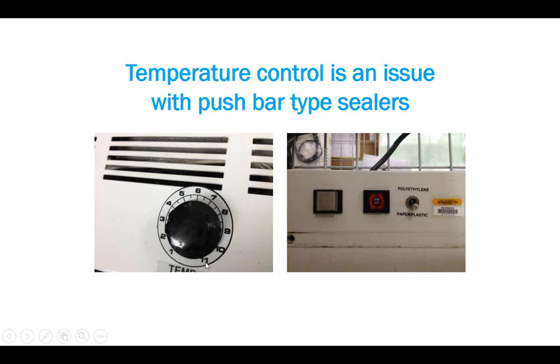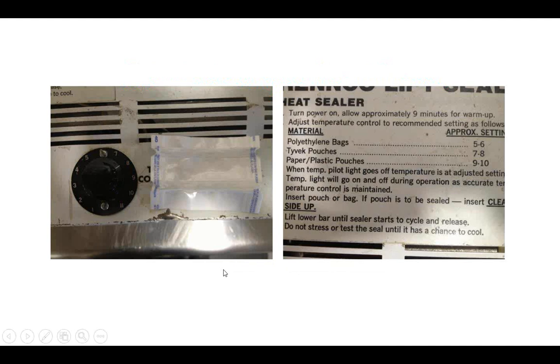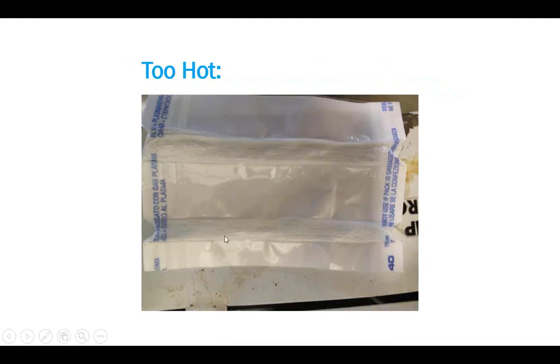I've seen some people say, 'Oh, it's a good seal, it's not a problem.' That is wrong, that is a bad seal. Here's an example, the next picture will be better. They just give you a number range, not a real temperature range, and no two companies have the same sealing temperature. If you turn it up too much, you will burn it, as you can see here, these are burnt where the temperature is too hot.